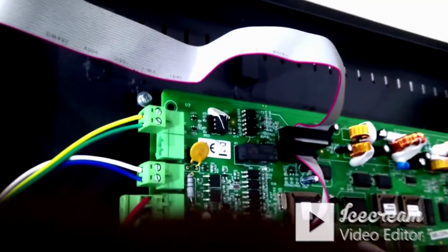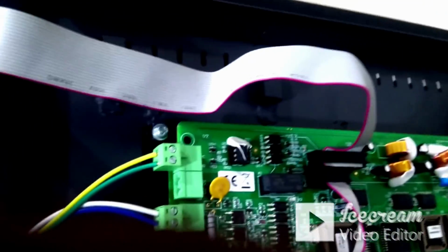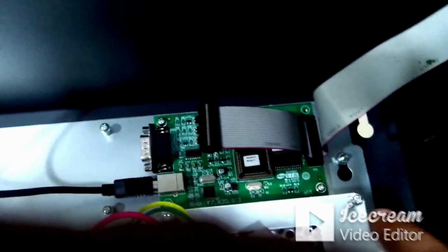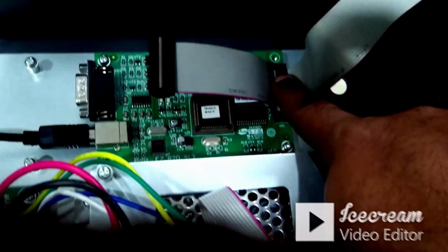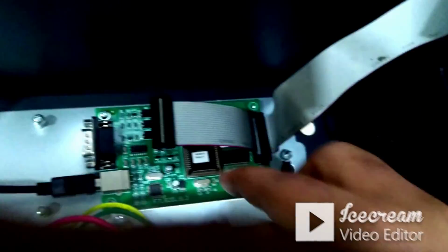In case you have two loop cards, in that scenario, from this extend port the ribbon cable will get connected with this RS232 card, and the ribbon cable comes with multiple slots, multiple ports. So the other end you can connect with the loop 2 also.